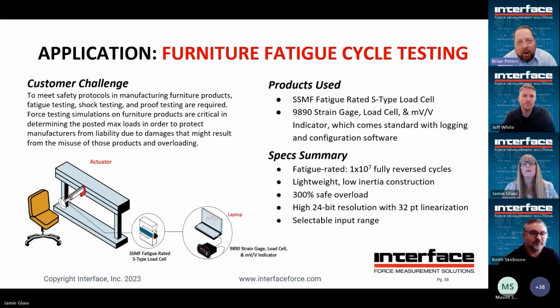Secondly, if you are often getting into that overload range and you can't avoid it, the best thing to start tracking would be your zero balance. If you start to see that zero balance shift, then that means you started to do some permanent physical damage, and you started shifting that output curve. It may still meet spec, as Keith said, but if you shift it too much, it may no longer meet the spec through the full capacity range.